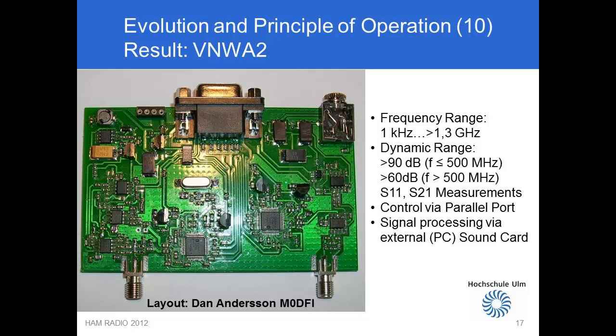It was controlled via the parallel printer interface of a PC, via the DB9 connector seen at the top of the PCB, and signal processing performed by an external sound card. With continuous frequency coverage from 1 kHz to 1.3 GHz, the dynamic range is more than 90 dB to 500 MHz and 60 dB above 500 MHz. Both measurements of S11 and S21 can be made. This is the basic concept of the VNWA and basically has remained unchanged up to now.